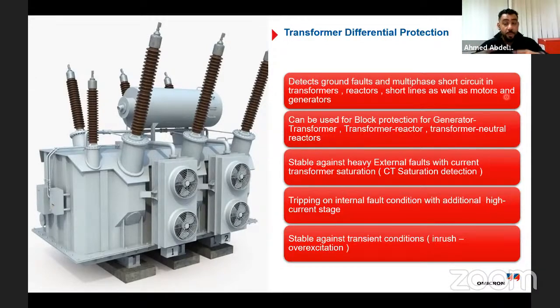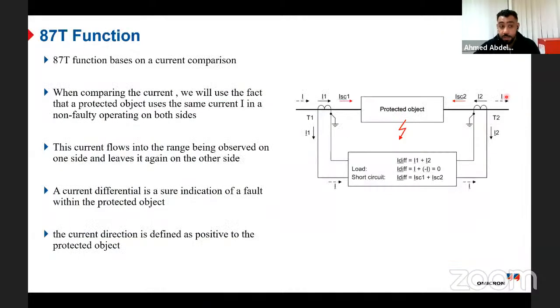The transformer differential can work in a block condition. That's why I need to say it's selective and also secure, because in the power plant, I have the generator very close to the transformer, the GSU, or we can say generator step up transformer. So if I combine both of them, generator and transformer, I can say this is a block or a unit. So I need a differential protection to work to cover all this block. So I call it block function. It must be stable against heavy external faults, because usually in the power system, I should have external faults and internal faults. And as we said, based on the physics, the protected zone in this slide is a defined area between CT1 and CT2, or T1 and T2. So if I have an external fault here outside, I can draw it with a pen. Just a minute here.